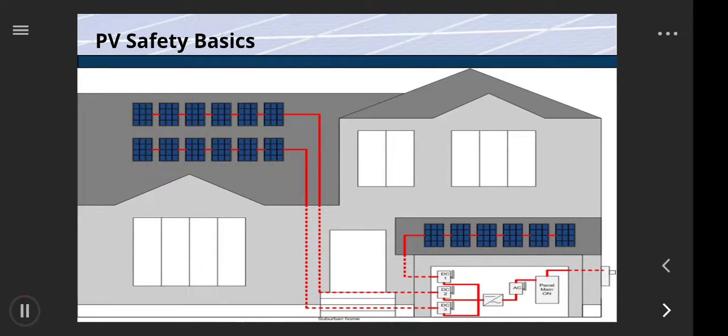The following is an example of a residential de-energizing sequence. When the AC disconnect switch to the inverter is turned off, the inverter subsequently turns off and a part of the circuit is de-energized. The switch handle is now in the down position and the wire is green to indicate a de-energized circuit. The main circuit breaker has been turned off and cuts all power to the AC disconnect switch.